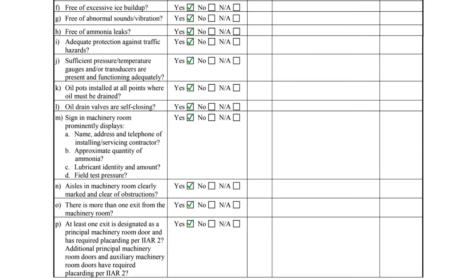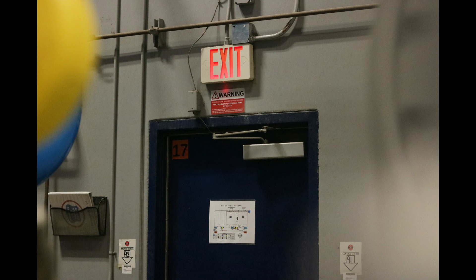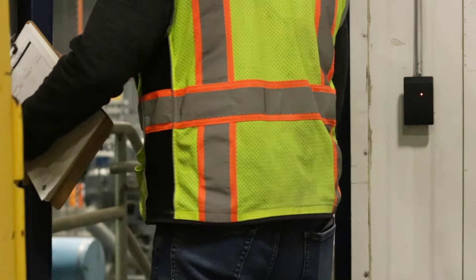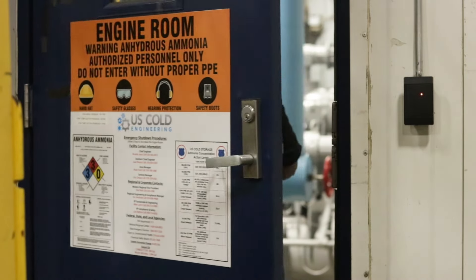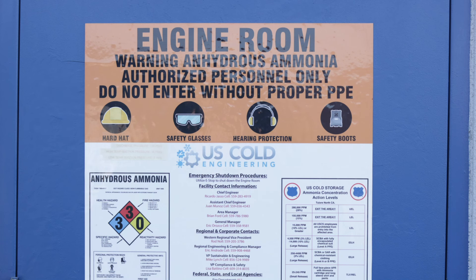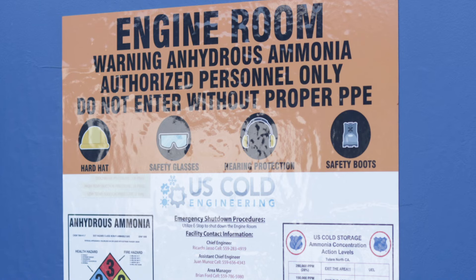Items O and P pertain to the machinery room exit doors. Item O asks if there is more than one exit from the machinery room. Item P asks if the principal and additional principal machinery room doors have required placarding per IIAR Standard 2. The 2021 edition of Standard 2 recommends that the machinery room doors must have the following signage: Refrigeration Machinery Room, Authorized Personnel Only, NFPA 704 placarding with a 3-3-0 designation, Caution Ammonia sign, and PPE requirements.